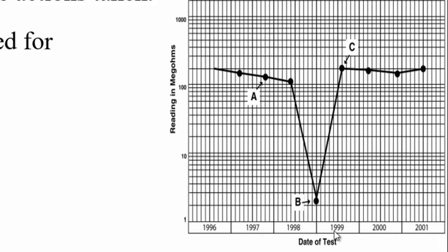So if you look at it from this particular point, you see a downward trend. The insulation is reducing. So if you are vigilant enough, that should tell you that something negative is developing within the equipment, and inform your decision on what to do to bring it back to normal.